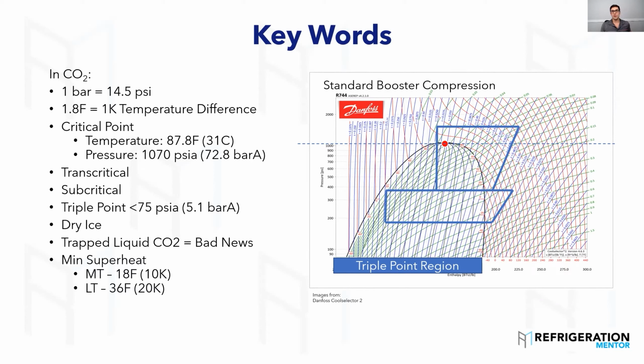You need to stay above that, because CO2 doesn't carry with the POE oil the same way as HFC. CO2 is very highly soluble in the oil. So what will happen is that if it has flinger feed, as it's going through the crankshaft or feeding the bearings, it'll start to wash them out. It'll start to dilute the oil when you get below that and cause issues.